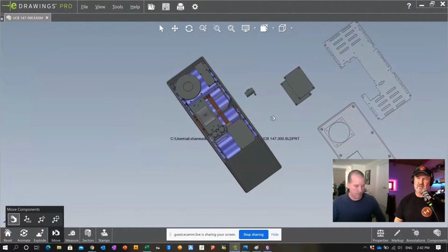At my place where it's sometimes 5 degrees in the morning, or less, we've only tested down to -10, but the cell manufacturer says the cells are okay to -50. I don't know if that's true since I haven't tested it, so we can only go on what we've tested. We allow -10 up to 60 degrees as the operating range. It doesn't degrade because of low temperatures, you just might lose a little peak power at lower temperatures. So -10 is pretty good, you can charge at full power at -10.